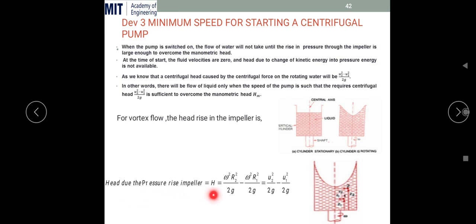Since u = rω, we have ω²r₂² = u₂² and ω²r₁² = u₁². So the head rise due to the impeller becomes u₂²/2g − u₁²/2g. This means whenever you have started the impeller, the head rise due to pressure is given by this equation: u₂²/2g − u₁²/2g.